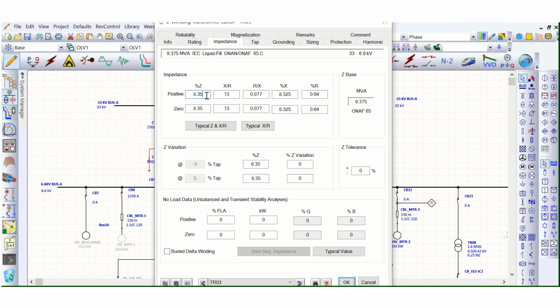So you need to change this impedance, otherwise your power system study will not be accurate. Your load flow study will get affected. Your short circuit study also, you need to correct this transformer impedance. You need to update this one. So if you have the transformer impedance, the ONAN rating impedance as well as the ONAF rating impedance, that will be the best solution.